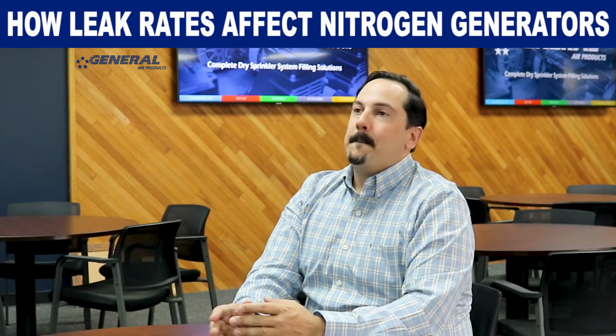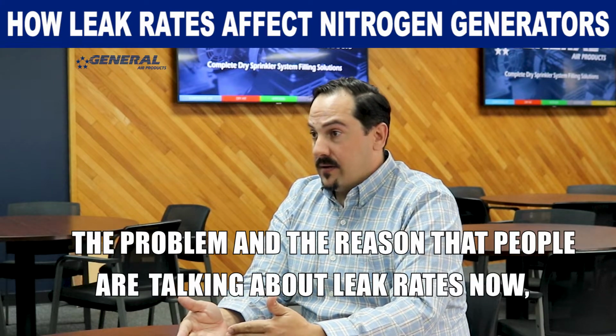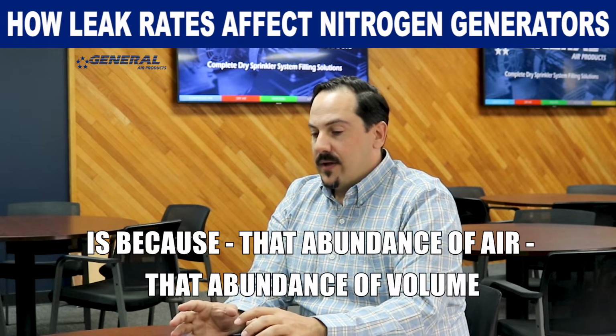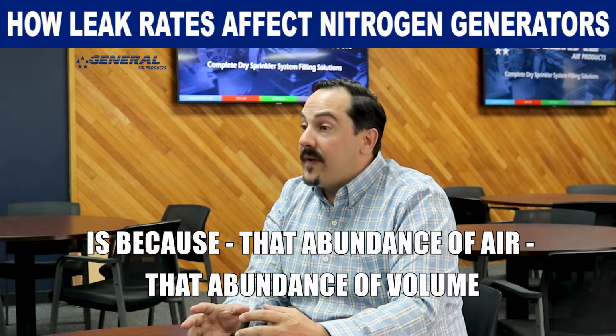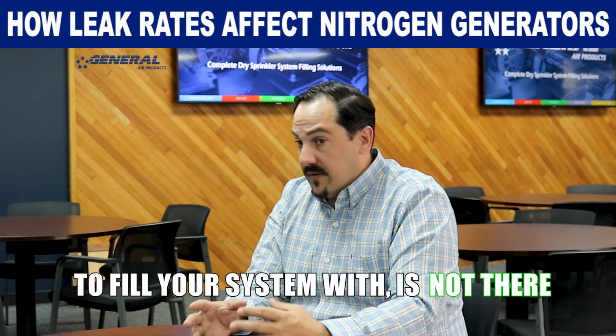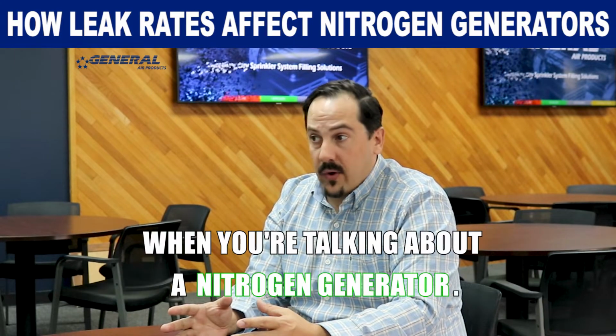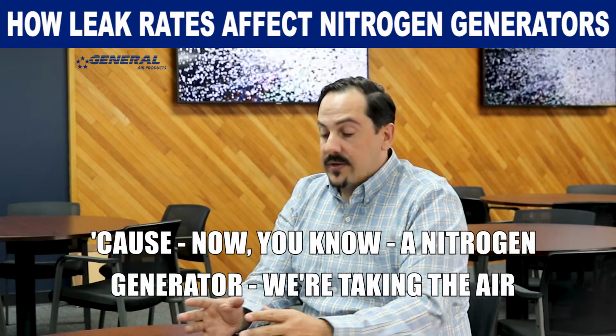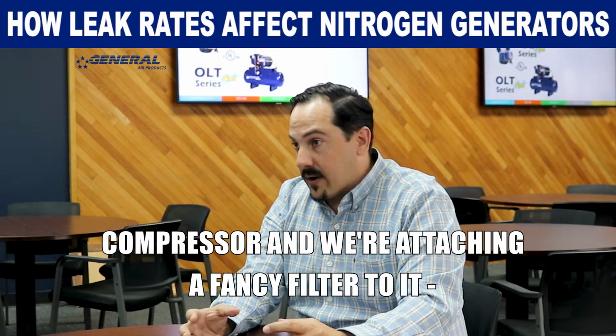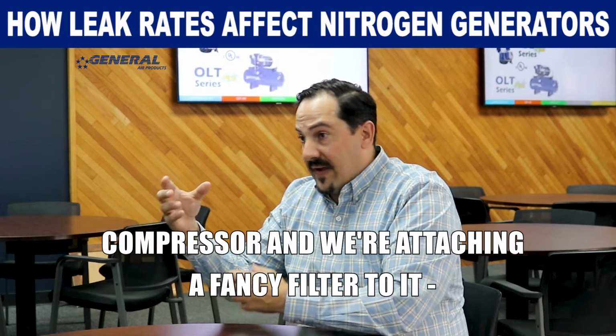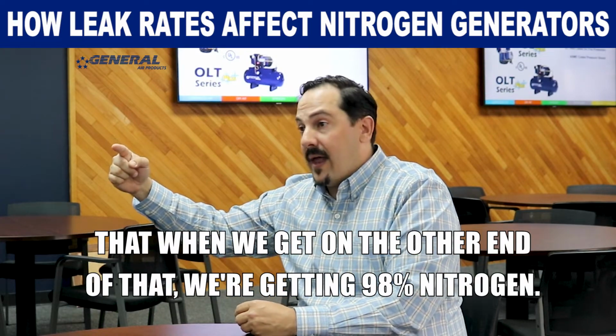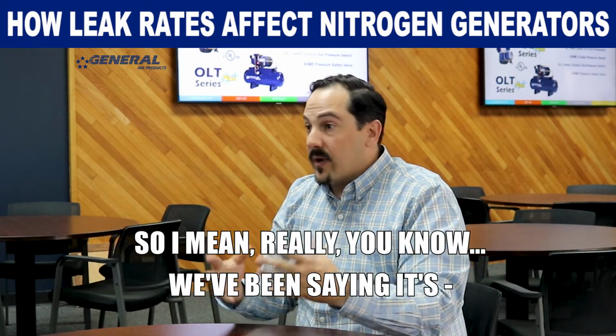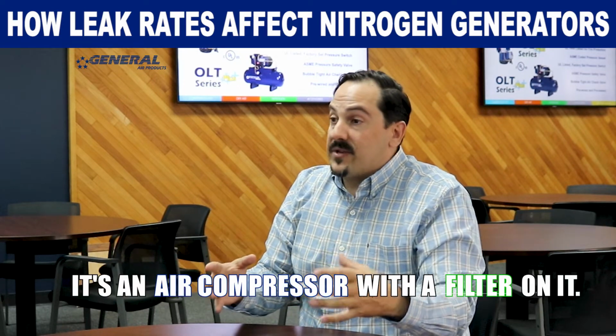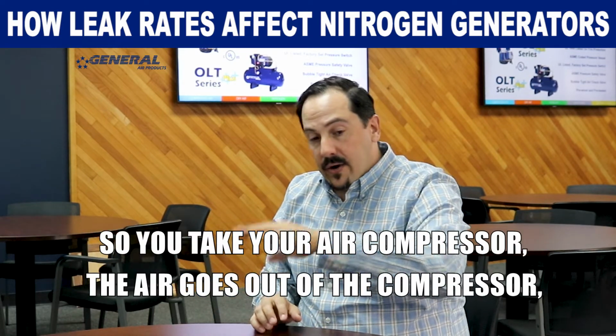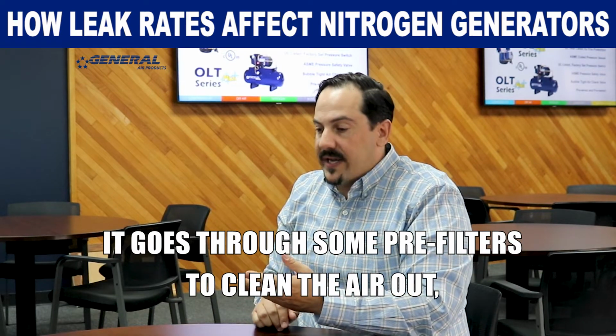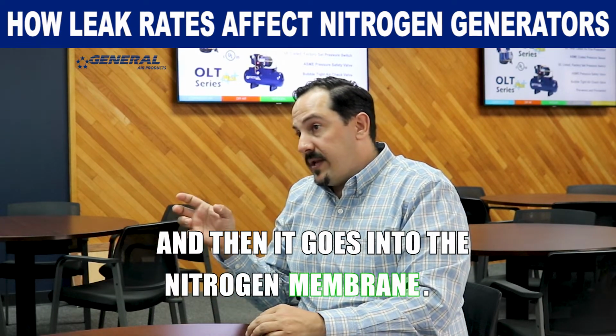The reason that people are talking about leak rates now is because that abundance of air, that abundance of volume to fill your system with, is not there when you're talking about a nitrogen generator. Because with a nitrogen generator, we're taking the air compressor and attaching a fancy filter to it, and on the other end we're getting 98% nitrogen. Really, we've been saying it's an air compressor with a filter on it. So the air goes out of the compressor, through some pre-filters to clean the air, and then into the nitrogen membrane.